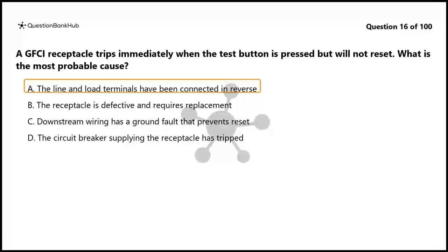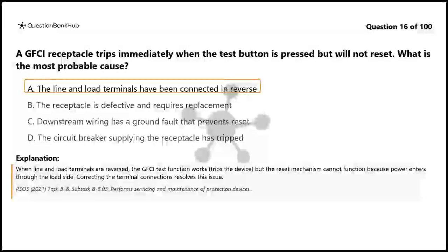The correct answer is A. The line and load terminals have been connected in reverse. When line and load terminals are reversed, the GFCI test function works and trips the device, but the reset mechanism cannot function because power enters through the load side. Correcting the terminal connections resolves this issue.